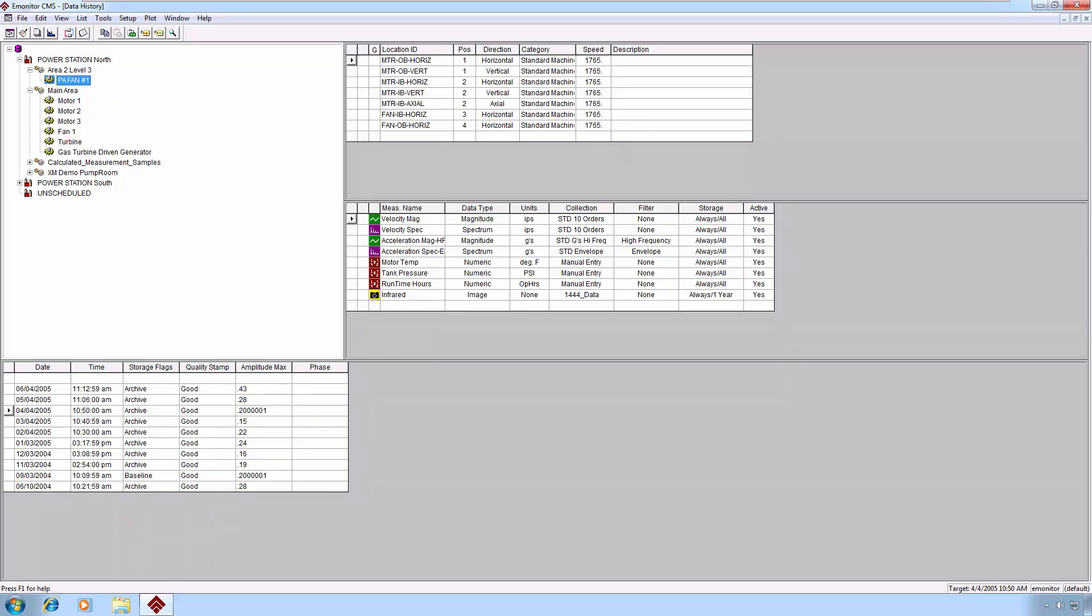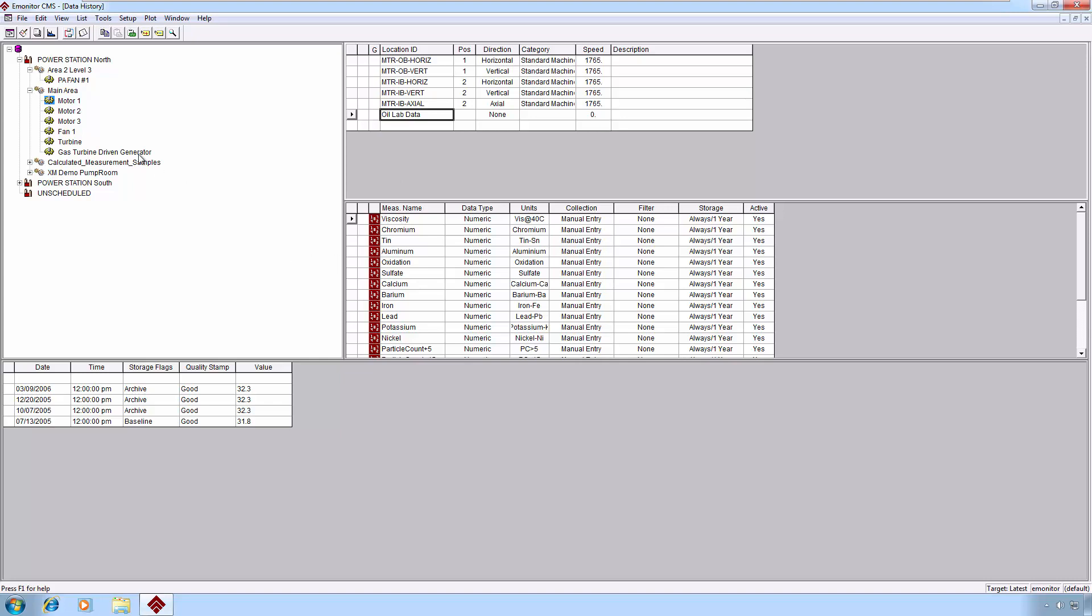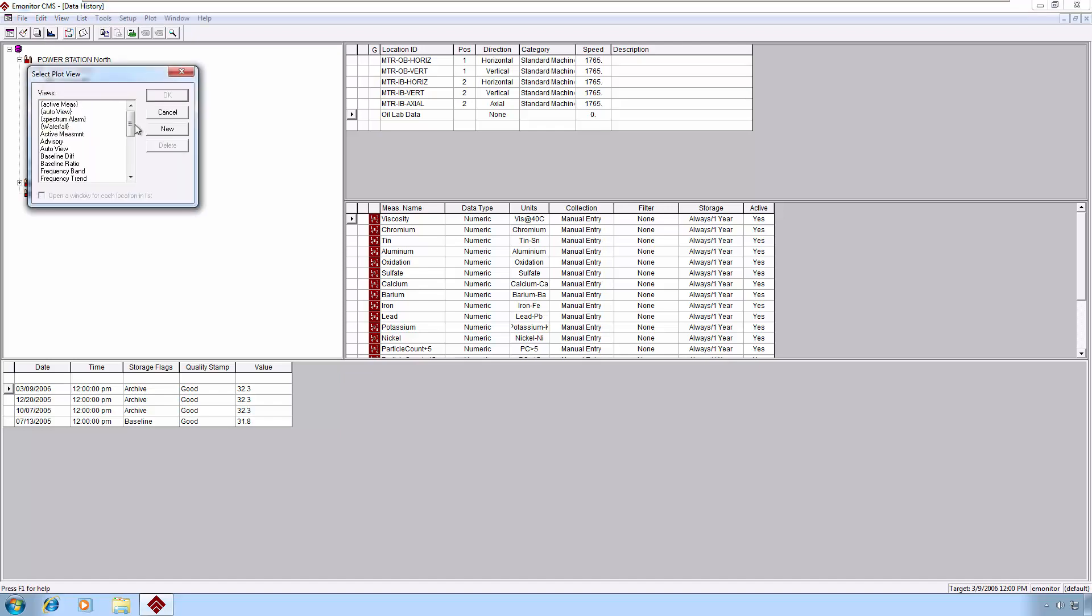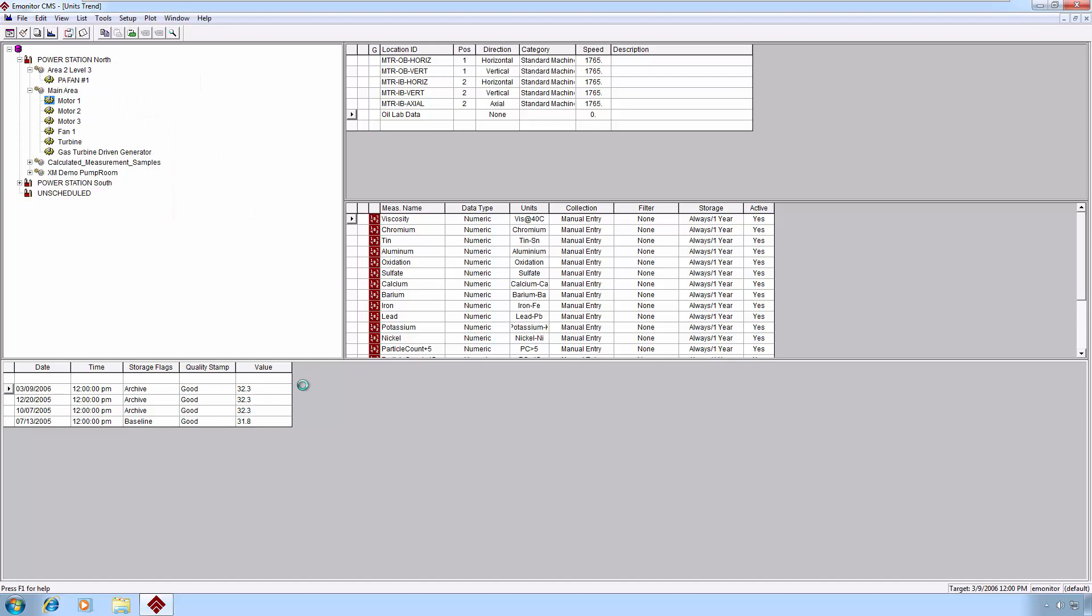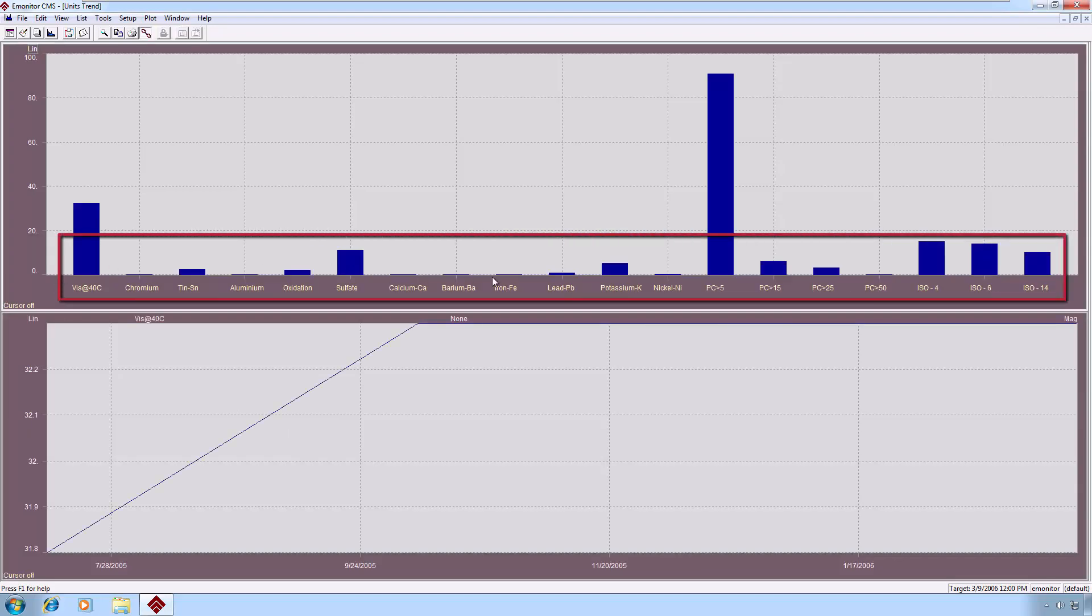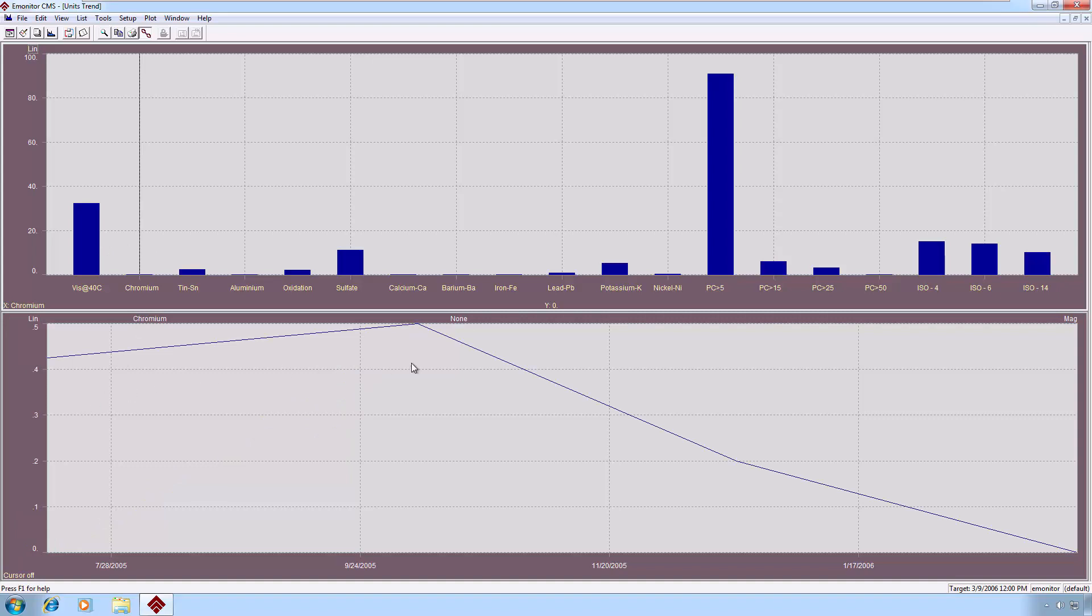A couple of other interesting plots. The units trend is designed for primarily oil data. You can use the units trend for really any kind of data. Let me give you an example. We will go to some oil data, since that's what this particular view is primarily geared toward. And if I pick units trend from the list, you'll see that I get all of the units, or in this case elements, that we are tracking in oil data on the top bar chart. And if I cursor a particular element, you'll get the trend of that particular element in the bottom trend chart.